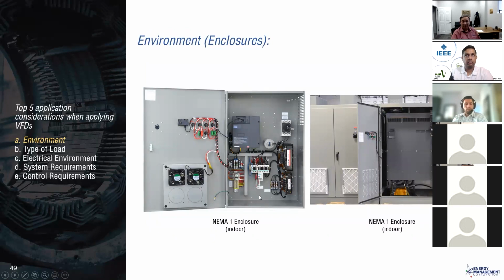And we said, well, we'll be glad to do that, but could we find a way to at least put that in an enclosure so that if you have issues down the road, you maybe need to replace the inverter, that at least you don't have to go back in that same footprint? Because that's the challenge of replacing older drive systems: some are very narrow and tall, and the footprints cause a lot of challenges. And you can't add a reactor, you can't add an EMI or RFI filter or those kinds of things.